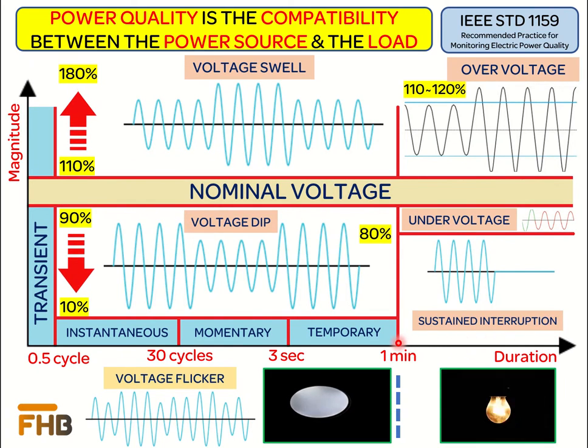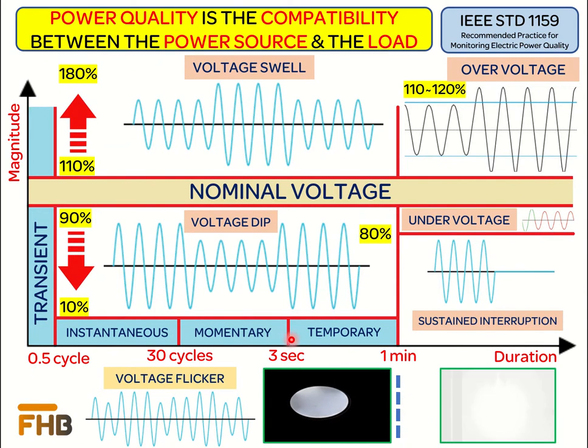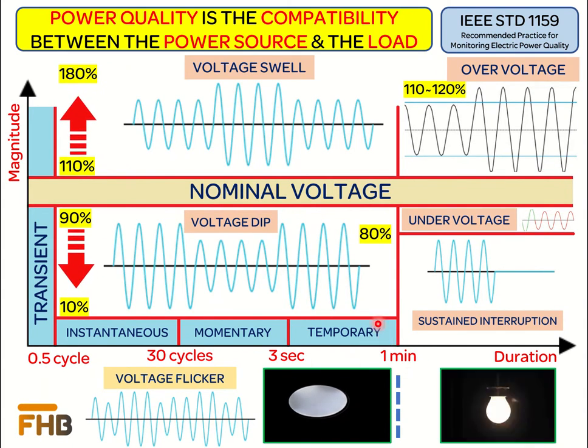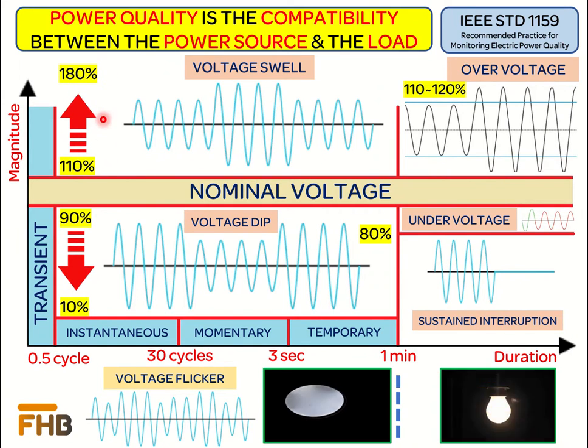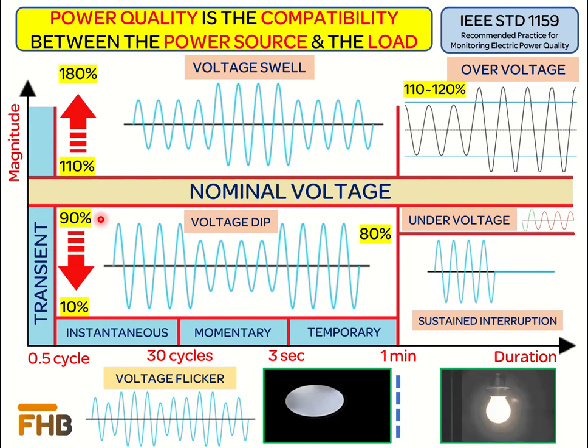Short duration variations can either be instantaneous, momentary, or temporary based on the duration as defined in the graph here. First, we will discuss the short duration variations in the voltage waveform. Voltage swell is the increase in RMS voltage at the power frequency for a duration from 0.5 cycle to 1 minute. Voltage sag or voltage dip is the decrease in RMS voltage at the power frequency for a duration from 0.5 cycle to 1 minute.